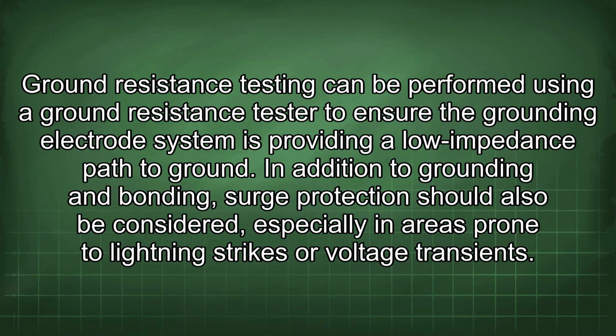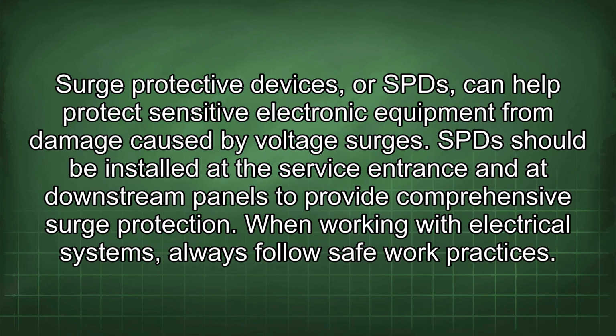In addition to grounding and bonding, surge protection should also be considered, especially in areas prone to lightning strikes or voltage transients. Surge protective devices, or SPDs, can help protect sensitive electronic equipment from damage caused by voltage surges. SPDs should be installed at the service entrance and at downstream panels to provide comprehensive surge protection.